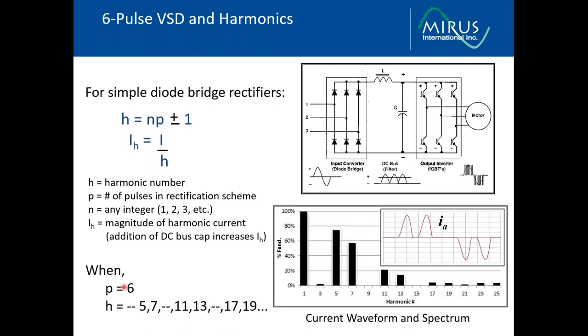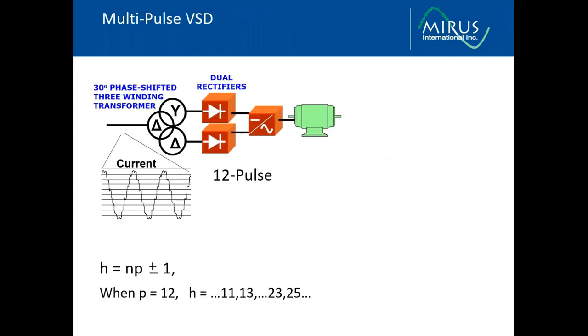So on a six pulse drive, when you substitute P equals 6 into this equation, you'll see that the predominant harmonics will be the 5th, 7th, 11th, 13th, 17th, and 19th. These are shown here on this spectrum, and the waveform is a typical double-humped Mickey Mouse ear type of current input drawn by the drive.